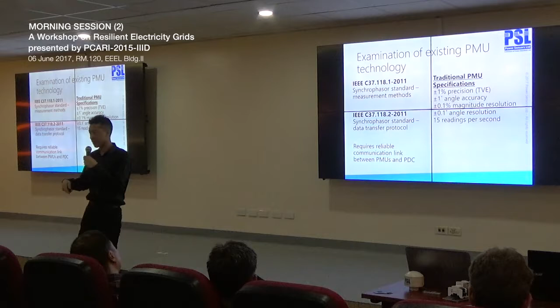Based on this information, we decided on a plan for how to develop a micro PMU. For a distribution-capable PMU, it needs to be precise enough because the cable runs are orders of magnitude shorter than what you'll find on transmission.